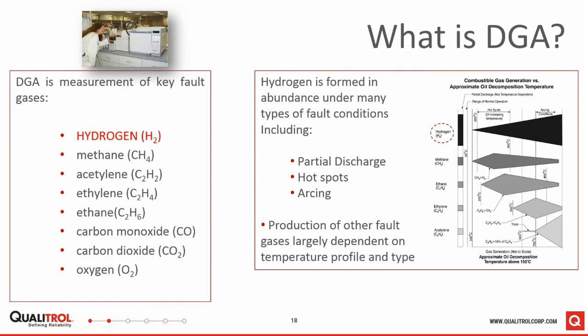So for our DGA product, we monitor hydrogen, and I've highlighted hydrogen here, and the question is, why hydrogen? The answer is that hydrogen is formed in abundance under almost all fault conditions. If you look at this chart on the right, on the y-axis it's showing the various different gases that are produced when oil breaks down, and on the x-axis it's showing a rough temperature scale. We can see that the first gases that are produced as temperature rises, and that can be associated with heat stress, are hydrogen and methane.